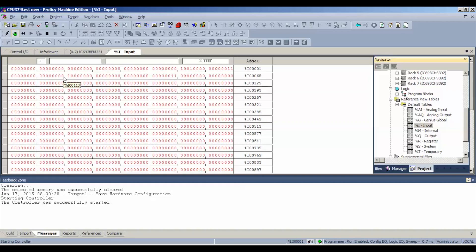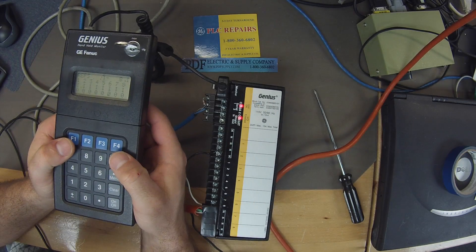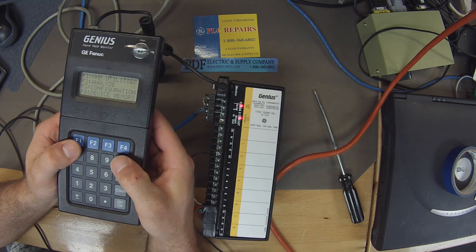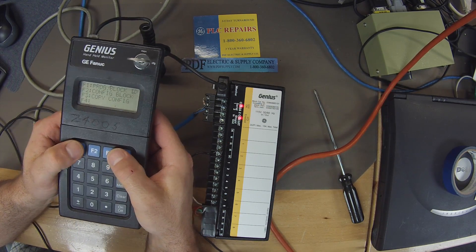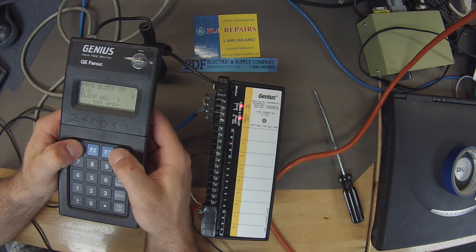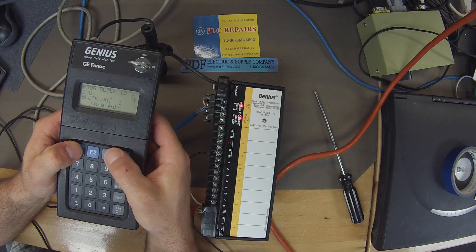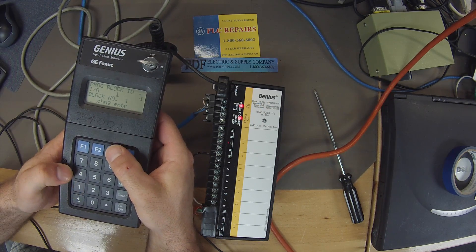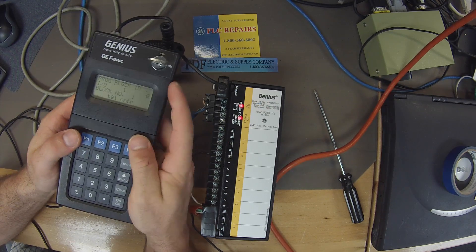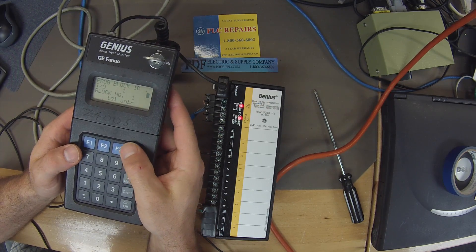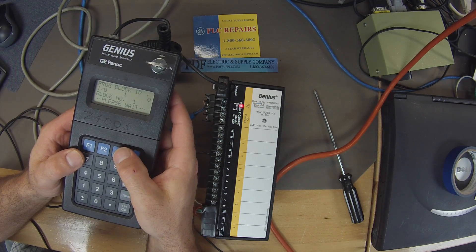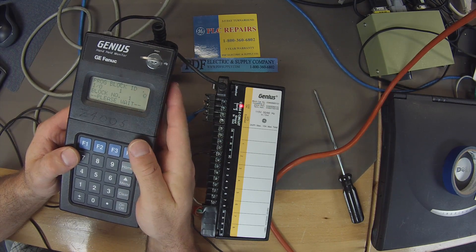Next thing, in the handheld monitor, I'm going to go back to home, F3 for configuration, F1 for program block ID, F1 for reference, enter, one, enter, and then toggle, F2, to output. You should have the Q there, then we hit enter. It's going to ask you to wait while it configures all eight outputs.